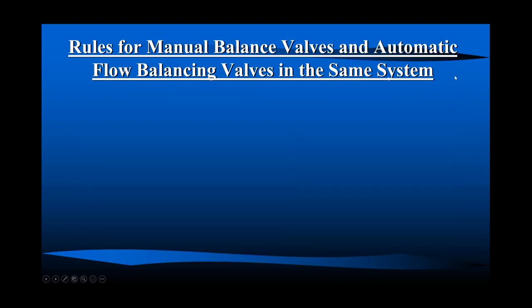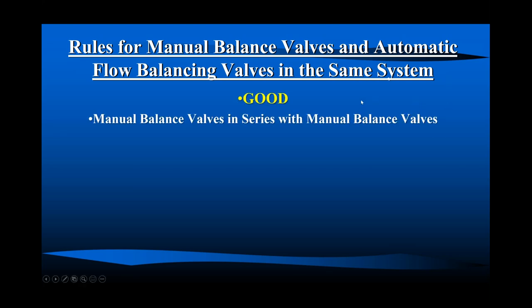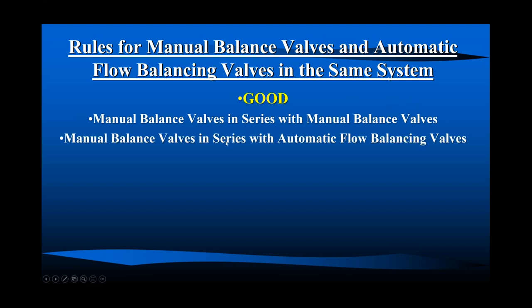So some basic rules should you decide to use automatic flow balancing valves, right? Some good rules: manual valves in series with manual balancing valves. Yes, we've seen this before, right? They're on the runout, the riser, and of course the terminal unit. So yeah, you should put manual balance valves in series with manual balancing valves. Manual balance valves in series with automatic flow balancing valves. Yes, we can do this.